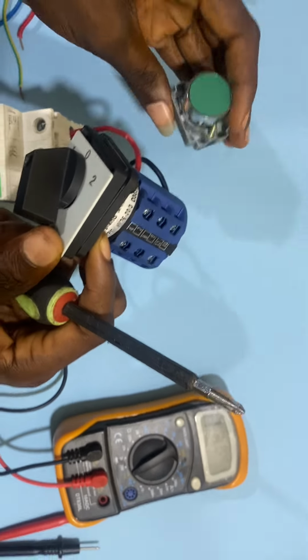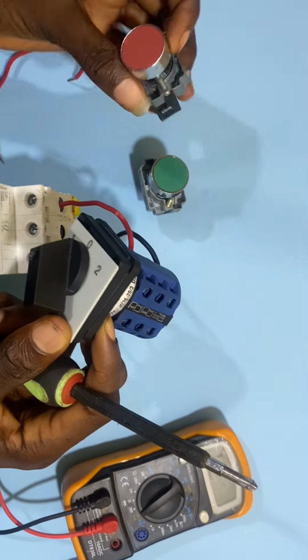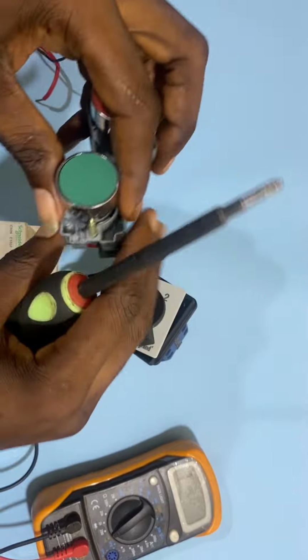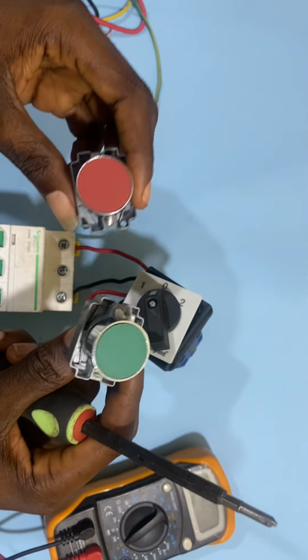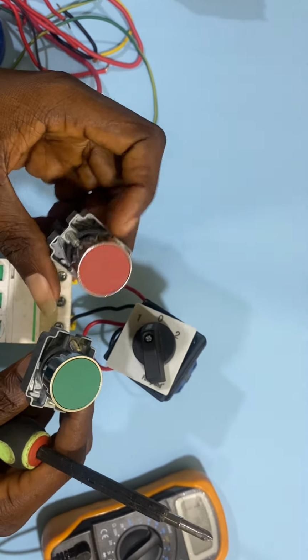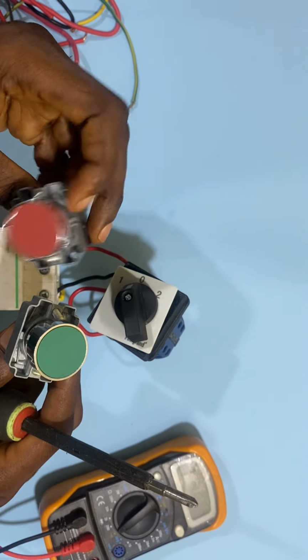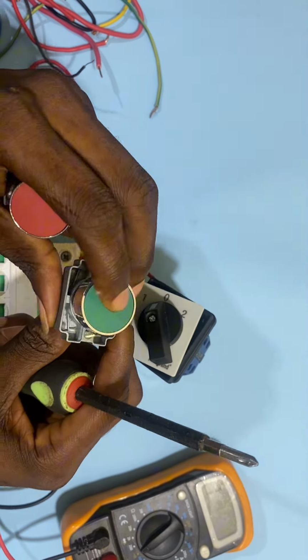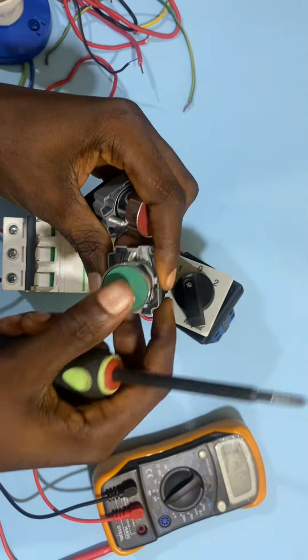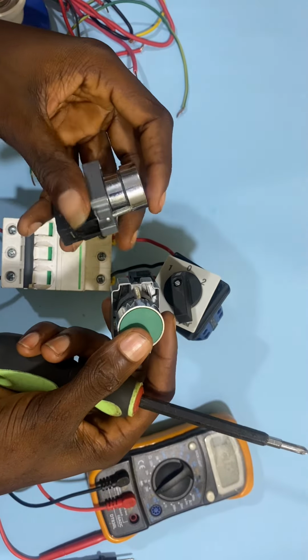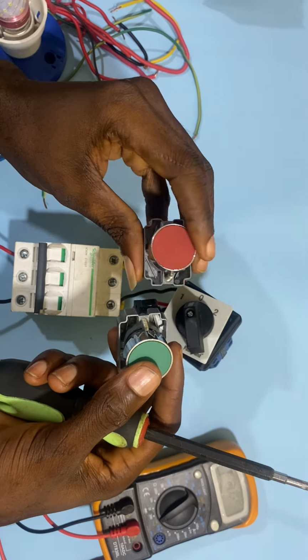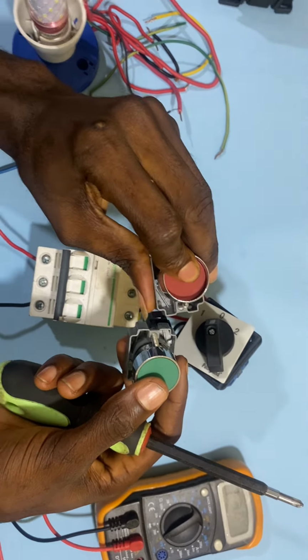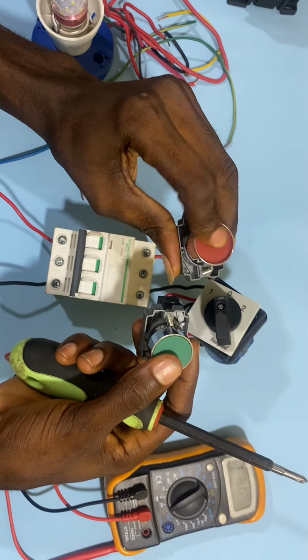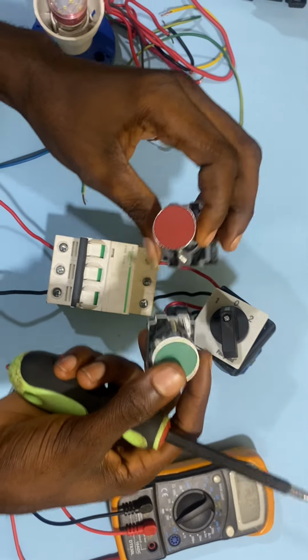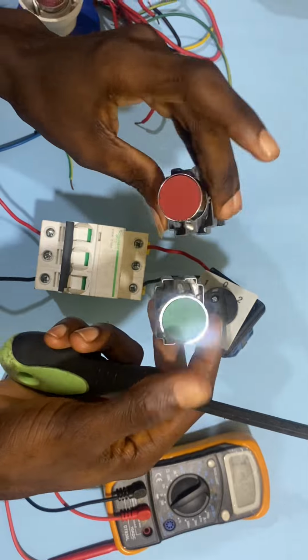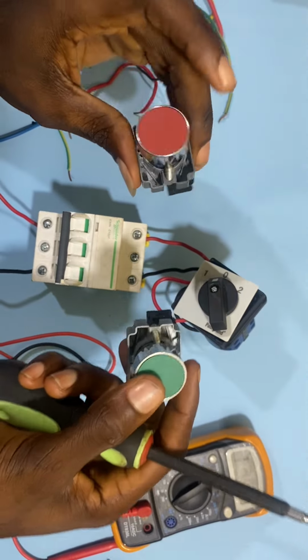So this is my start button and this is my stop button. My start button at the initial stage is always normally open, whereas the stop button at initial condition is always normally closed. So when you press the start button down, that is when the terminal is connected. Here it is always connected at initial condition, but when you press it down, it will disconnect, and when you leave it, it will connect and allow voltage to pass through it. Check our previous video, you will see the explanation of this start and stop button.